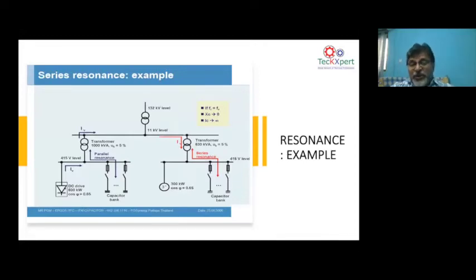In this photograph, you can see the factory on the right side does not have any variable frequency drive. This poor guy has only a motor. He does not have power electronics. He has not purchased a VFD. But look at his neighbor on the next side. The neighbor has a DC drive in his plant. Now you can see the neighbor is producing harmonics. You are not producing harmonics. And that neighbor's harmonics come into your factory and create a series resonance.